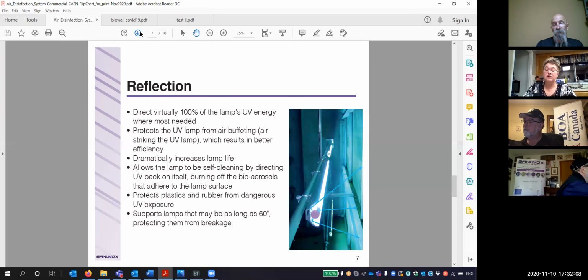Now, in ASHRAE, in their chapter, they also have a chart of reflective qualities of different materials. So when we take a look at the ductwork, this is really important - this is a huge contribution to the sizing. If you have galvanized steel as ducting, it's only 25% reflective, and we do have a reflection coefficient that we input in our calculations when we're doing it. But if you upgrade the ductwork to aluminum, aluminum is highly reflective. All of our extrusions and this deflector on this unit shining on this coil are made out of aluminum. It's 85% reflective, and it enhances that germicidal treatment of breaking the RNA of the COVID-19.